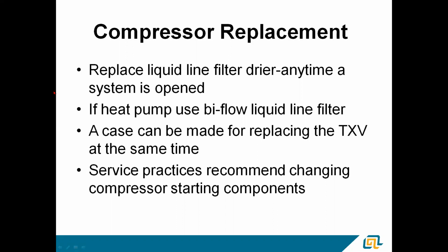I have found that if the first compressor fails in 2 years, the replacement compressor will usually fail in a year, and so on. They get faster and faster. So really have to address the problem, not the symptom. Service practices always recommend changing all compressor starting components and contactors. Again, this is one that your company is going to have to make their own decisions on how they go forward with it. If by some chance you're doing a warranty replacement, I don't think it's even a concern. Just go ahead and replace them. Take every precaution you can that that system will not have any kind of repeat failures.